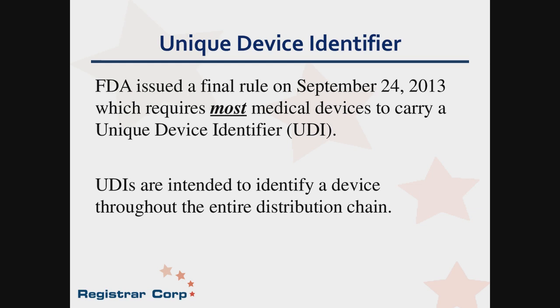So the FDA issued the final rule for the unique device identifier on September 24th in 2013 and made it mandatory that most medical devices have to carry that identifier on the label. And the reason for that is that FDA really likes to track a medical device from the place where it is manufactured to the place where it is used.